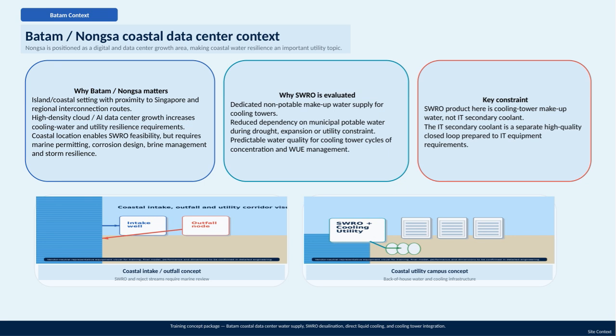We evaluate SWRO because it offers a dedicated source of non-potable water for cooling towers, reducing reliance on municipal potable water, especially crucial during droughts or facility expansions. Additionally, SWRO provides predictable water quality, which helps maintain efficient cooling tower cycles and overall water use effectiveness. One key constraint to note is that the SWRO output is intended specifically for cooling tower makeup water, not for the IT secondary coolant system.